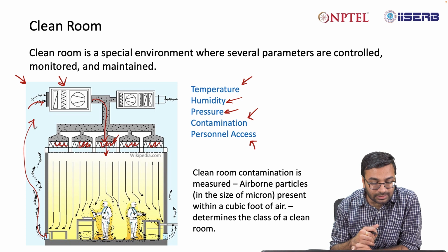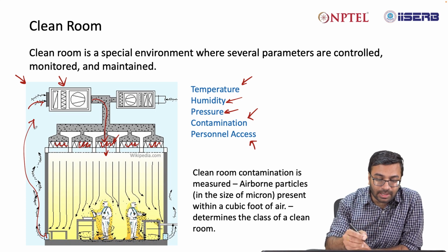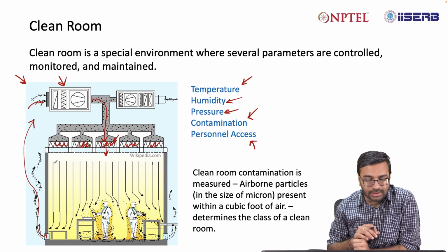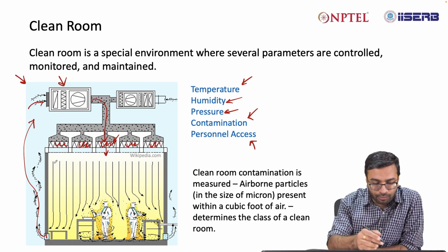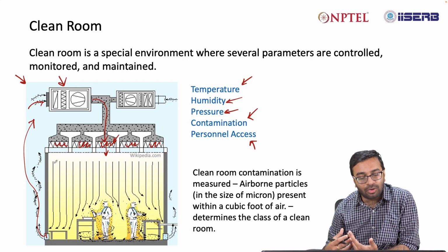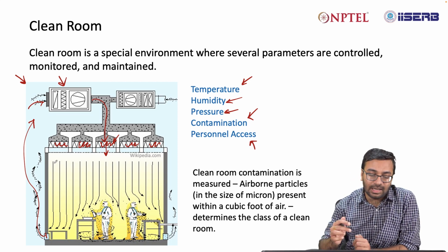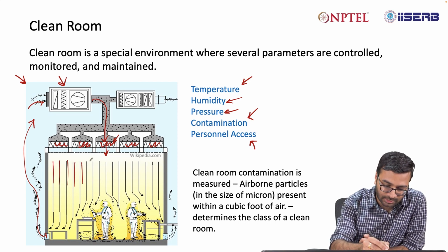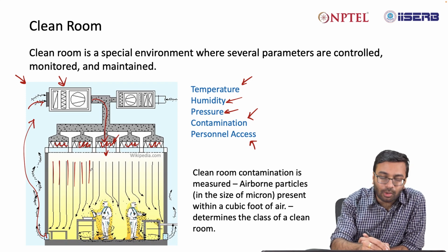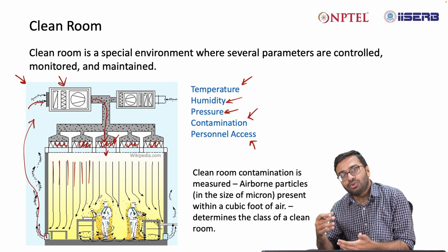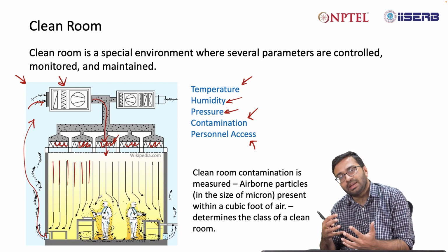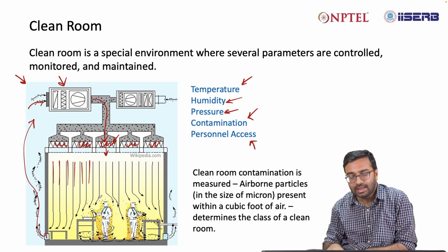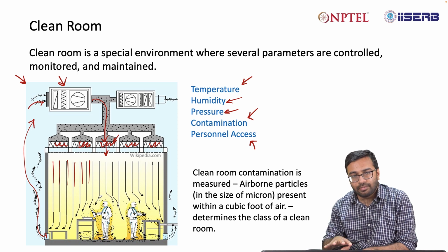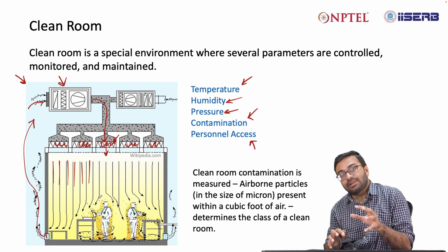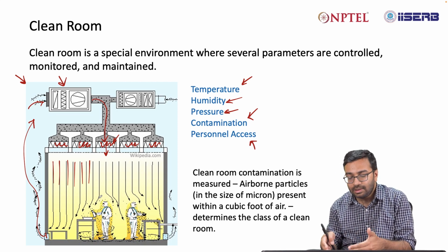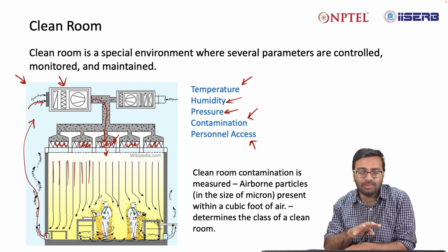And the second thing that is very important in this case is that we maintain a laminar flow of air inside the room. So what is a laminar flow? Laminar flow is a flow that is in order. It's a fluid mechanics term, and I am not going into details of that. In short, a laminar flow is where the velocity profiles are like this, and there is no turbulence in the environment. The problem with turbulence is that turbulent air usually creates an environment which is very dusty. For example, on this table or wherever you are sitting, if there are dust particles, and if the air flowing here is very turbulent, then these dust particles will again come into the air circulation. That is why laminar flow is preferred.